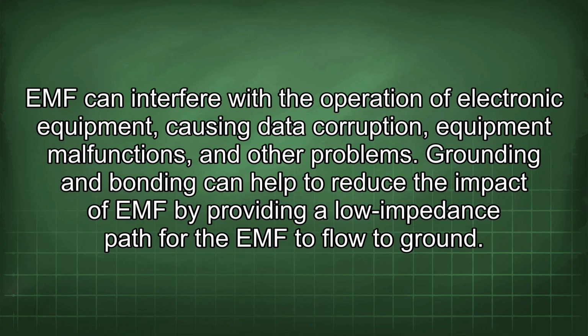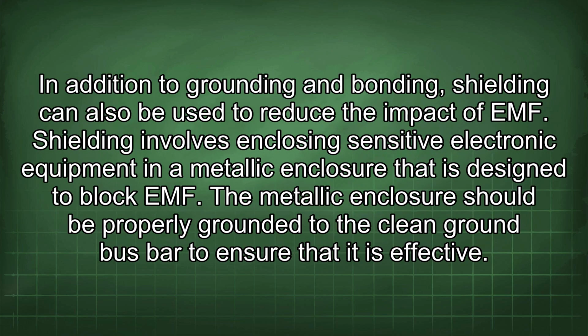In addition to grounding and bonding, shielding can also be used to reduce the impact of EMF. Shielding involves enclosing sensitive electronic equipment in a metallic enclosure that is designed to block EMF. The metallic enclosure should be properly grounded to the clean ground bus bar to ensure that it is effective.